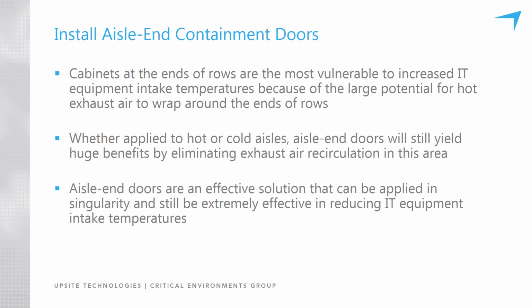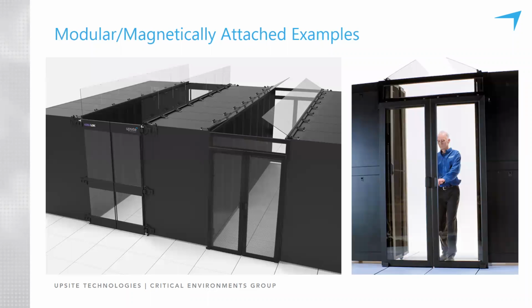As I like to say to people, if you have a limited budget, the first thing to do is buy blanking panels, and the next thing to do is buy doors. After that, think about a roof or baffles on top of the cabinets, because doors alone create a lot of benefits. We'll take a look at a couple of different options for doors. In the image on the left, we see a hot aisle and then a cold aisle.